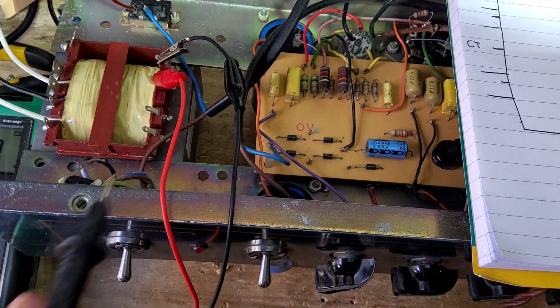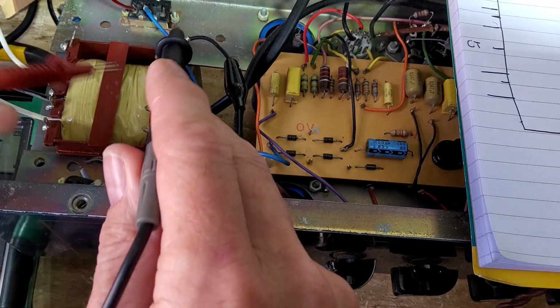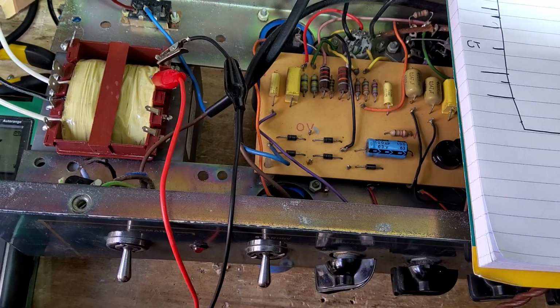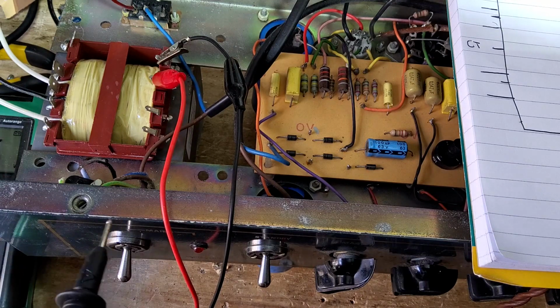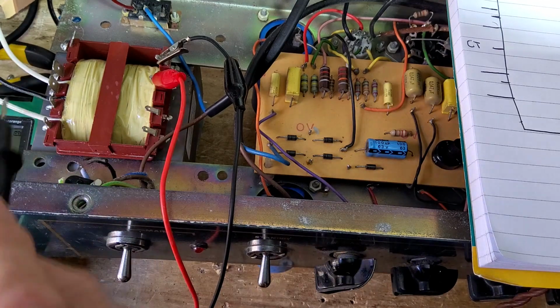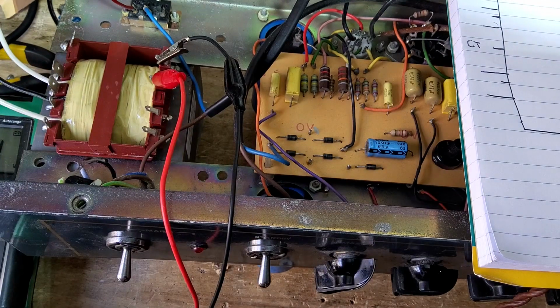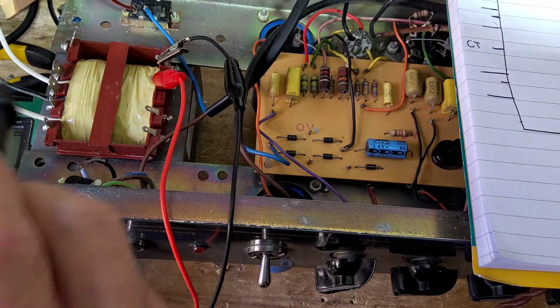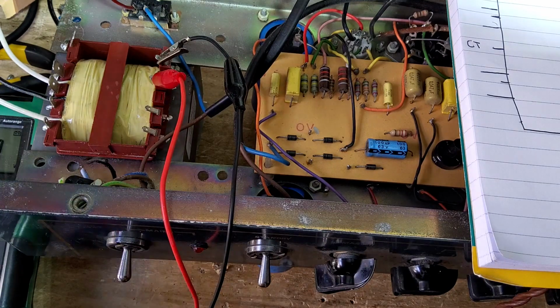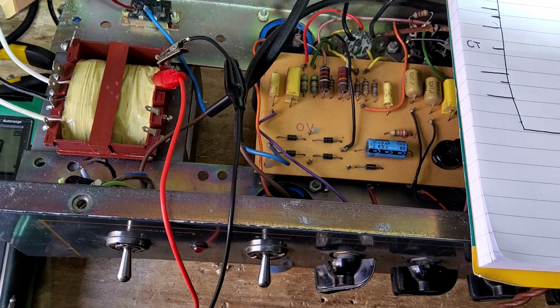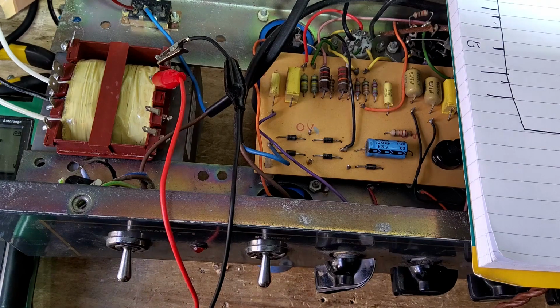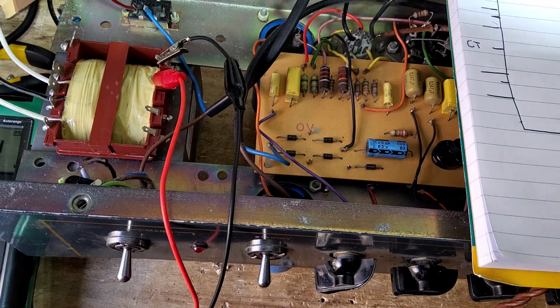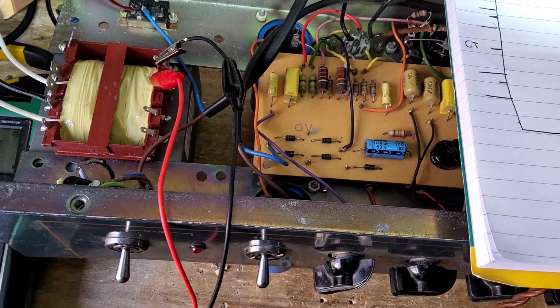So I'm going through this transformer, testing the individual tap-ins against one another to try and find the right combination. This can be quite dangerous. A typical example: I tapped onto one of these windings, and when I tested it I got 247 volts with only 15 going in. That tells me that's not the right way to have it connected, but it also tells me that if I'd touched those terminals I'd have got quite a nip off that.